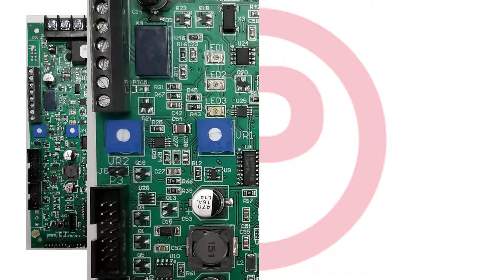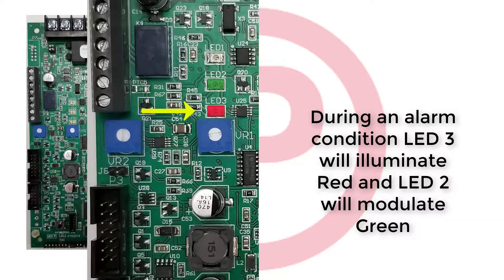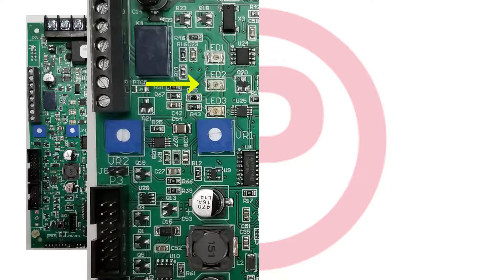If the system is activated upon an alarm condition, LED 3 will illuminate red indicating an alarm while the green LED will modulate. The intensity of the green LED will vary upon the level of the broadcast, or if the mic is keyed, the green LED will dim.